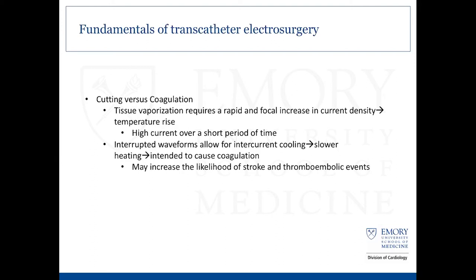It uses Bovie cautery, so there's two important parts here. One is cutting versus coagulation. Tissue cutting is the goal of transcatheter electrosurgery, and that's achieved by using tissue vaporization. So you have a rapid and focal increase in the current density that allows for a temperature rise, and then you have a high current over a short period of time, and you're able to perform cutting. If you're on coagulation mode, what you have is an interrupted waveform. There's intercurrent cooling, slower heating, and that's intended to cause coagulation, which for endovascular work, if you coagulate in a blood vessel, you increase your risk for stroke as well as your risk for thromboembolic events.